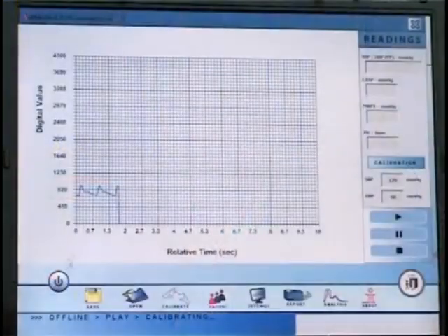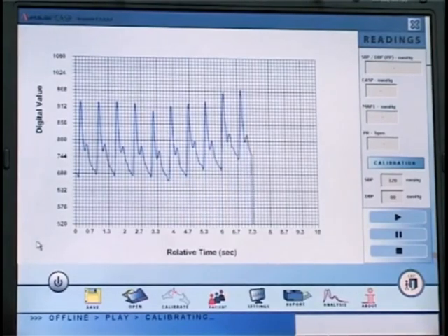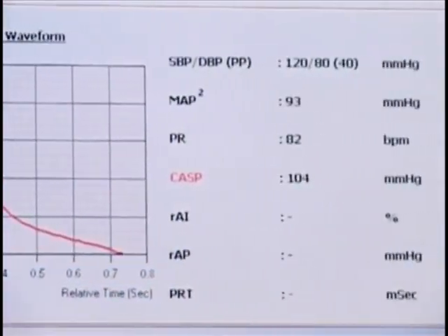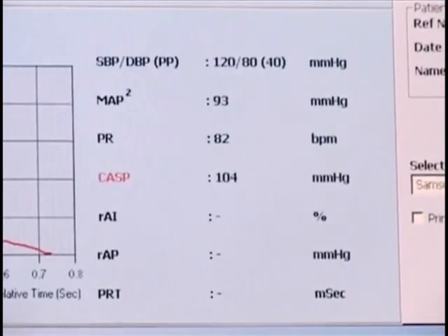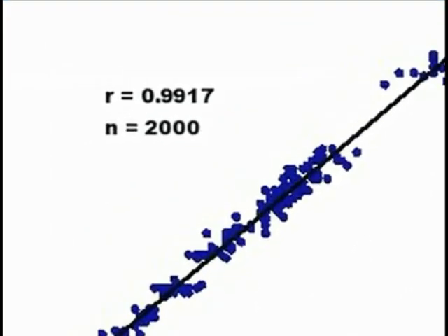Imagine achieving that kind of accuracy across 10,000 patient waveforms. When we carried out the invasive validation using a protocol written by Professor Brian Williams, a catheter was placed at the root of the aorta while BPRO was worn on the hand of patients undergoing angiogram. For every wave, continuously wave for wave, we measured the central pressure invasively and read off the central pressure as calculated by BPRO. With 2,000 patient waveforms, the accuracy was 0.9917 — which is remarkable.